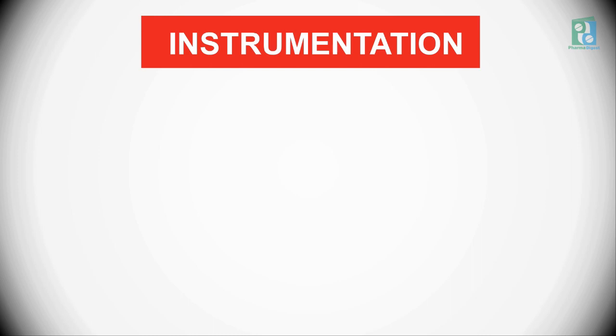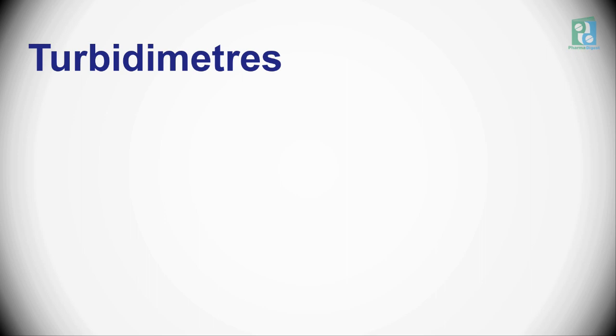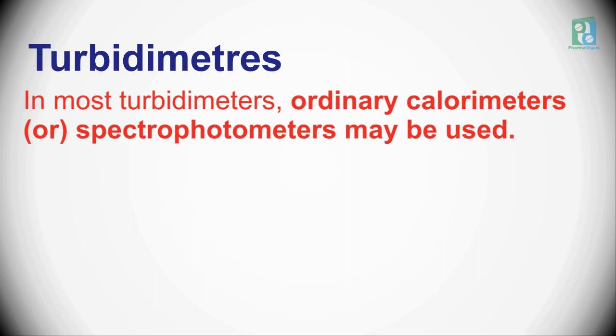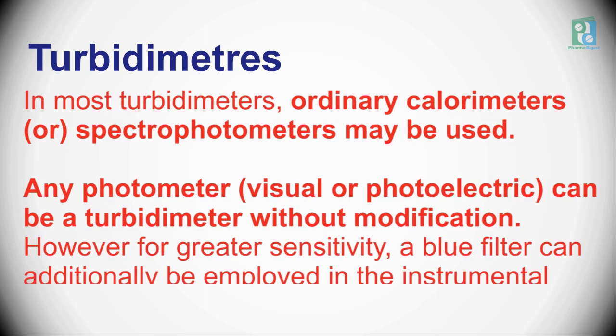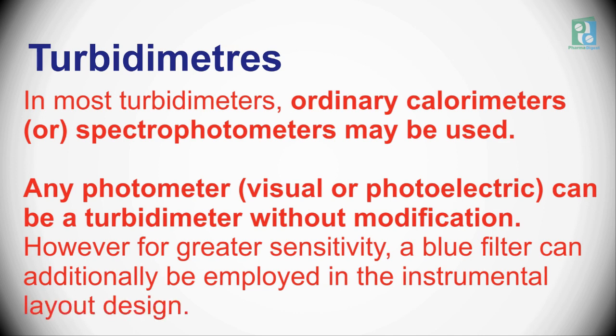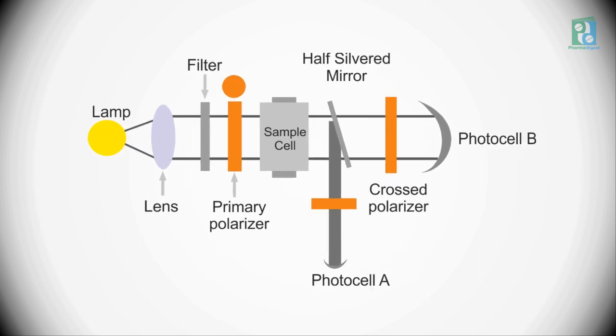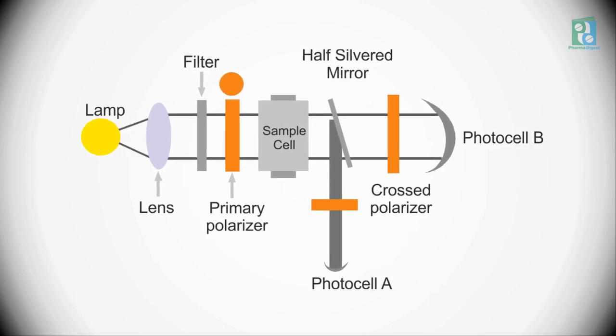Let's see the instrumentation of Turbidimeters and Nephelometers. In most turbidimeters, ordinary colorimeters or spectrophotometers may be used. Any photometer, visual or photoelectric, can be a Turbidimeter without modification. The instrumental layout design includes a lamp, lens, filter, primary polarizer, sample cell, photo cell A and photo cell B, half-silvered mirror, and crossed polarizer.